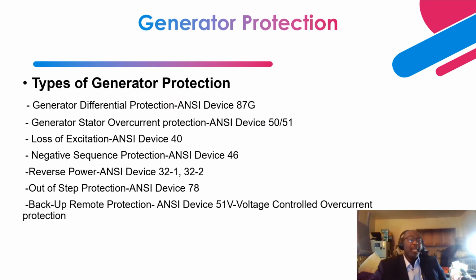Okay, so in the previous slide, we talked about all the abnormal conditions that basically require protection for the generator. Now let's talk about the electrical protection, right? Okay, so the main protection for the generator is differential protection, right?